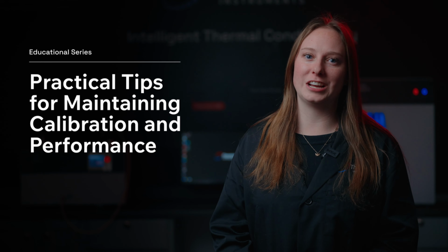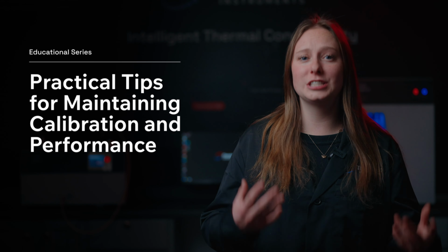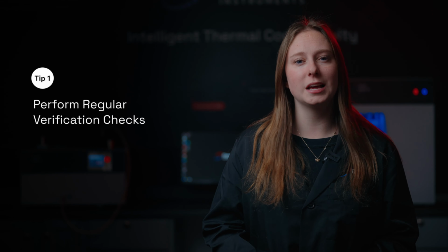Always perform a verification test after calibrating a unit and continue verifying periodically during routine use. Verification confirms that the calibration worked correctly, and it helps identify early signs of drift. Heavily used instruments, or those exposed to challenging materials, may require more frequent checks. Tailoring verification to your usage helps balance accuracy, efficiency, and downtime.